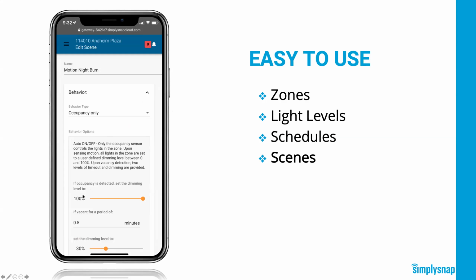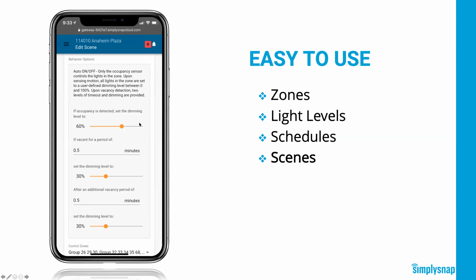This is an occupancy scene. When occupancy is detected, the lights go to 100%. If I want to change that, I scroll down and change my occupancy level to 60%. I can also change the timeouts, 30 minutes, 5 minutes, an hour, that Michael mentioned. That's all configurable, so very flexible depending on what the customer needs.